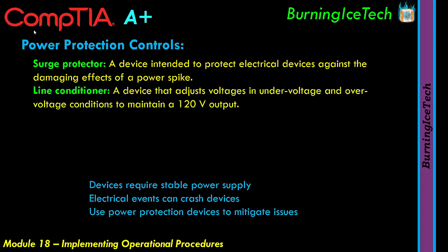The second one we can make use of is a line conditioner. These aren't something you'll find very often; quite frankly, they're normally built into other devices like UPSs, uninterruptible power supplies. But what is a line conditioner? It's a device that adjusts voltage in under-voltage and over-voltage conditions. If voltage is too high, it brings it back down to the approximate amount, say 120. If it's too low, it'll bring it up to 120 where it needs to be. That's its purpose, but it's the only thing it does.